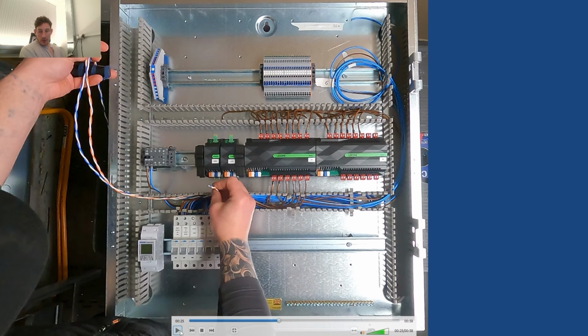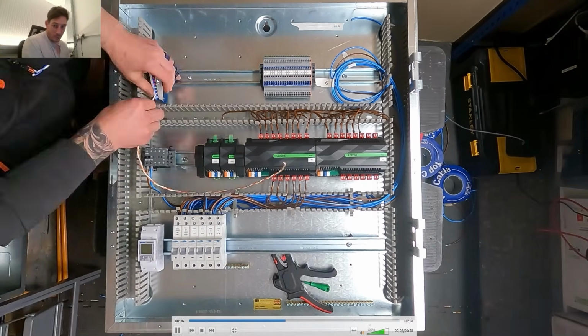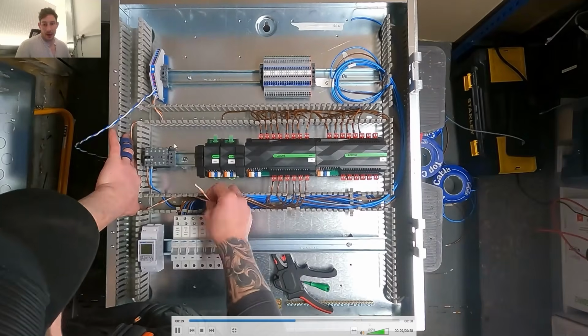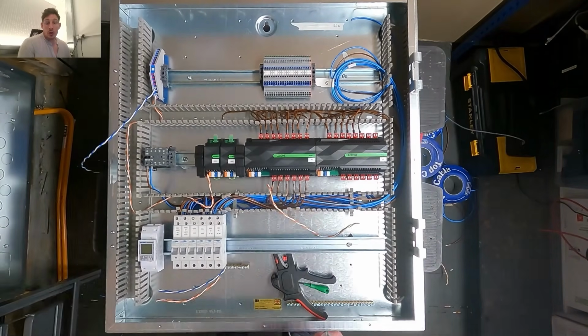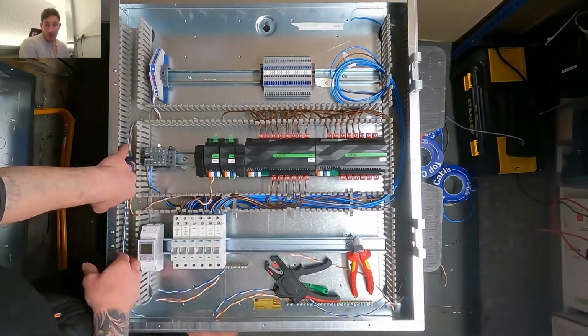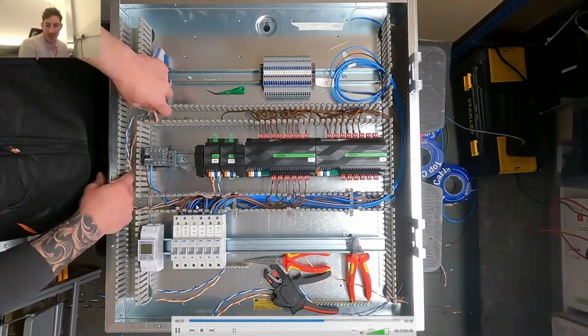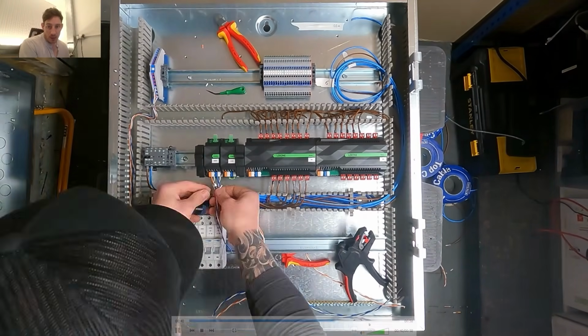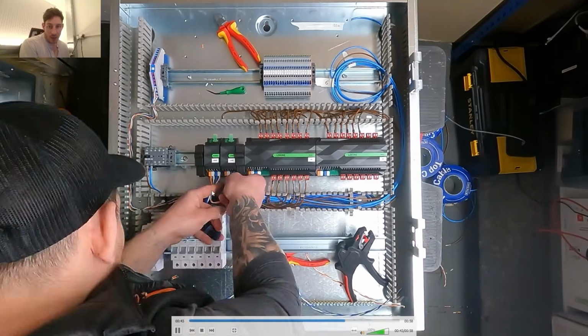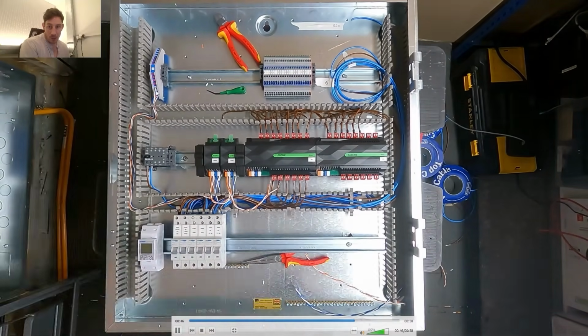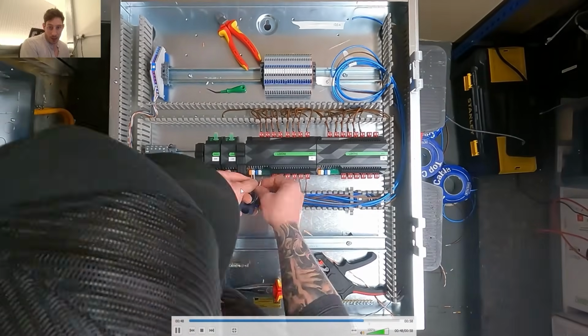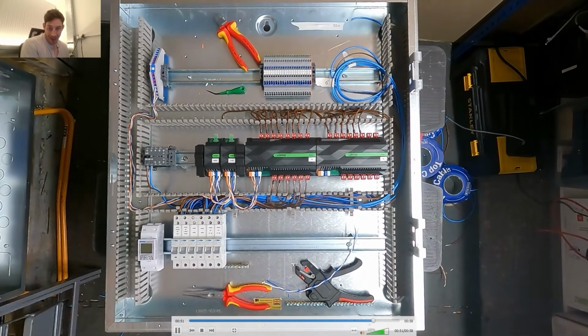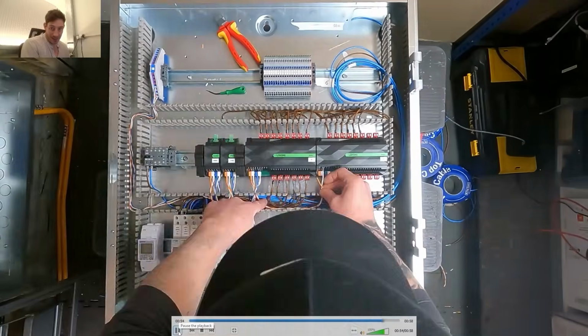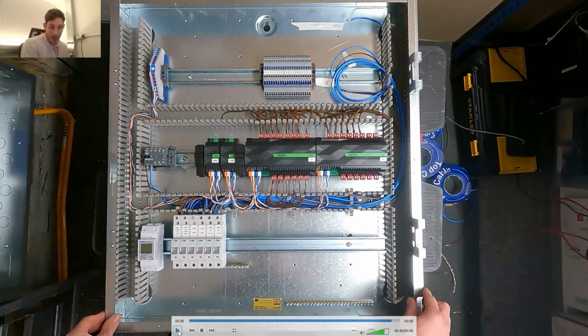So as you can see here, I took a master length and I'm wiring in the 24 volt DC extension power. The orange white twisted pair, I'm going from this terminal, in, out, in, out, in, out. At the same time I'm doing exactly the same thing with the blue and white twisted pair for the Lox link, and they're both coming in on this terminal.